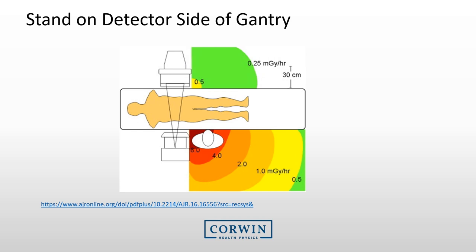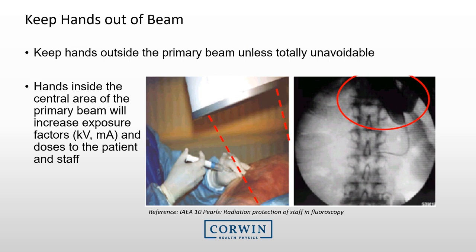From a top-down view, when x-rays pass through the patient toward the detector, backscatter returns toward the operator on the x-ray tube side — making that the highest exposure area, while the detector side is the lowest exposure area. Also, keep your hands out of the radiation beam. When hands enter the beam, the system automatically detects additional material and increases the radiation output — raising radiation exposure both to your hands and to the patient.